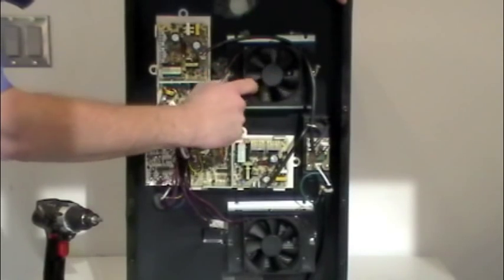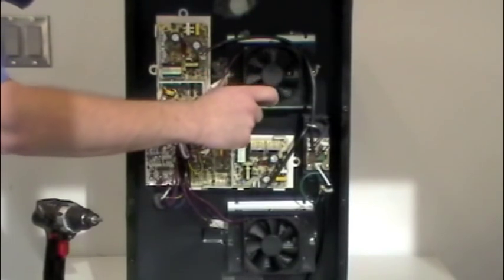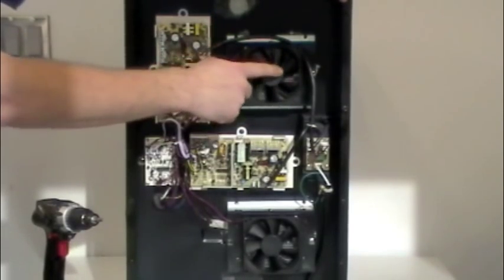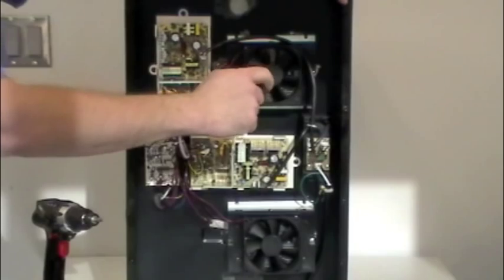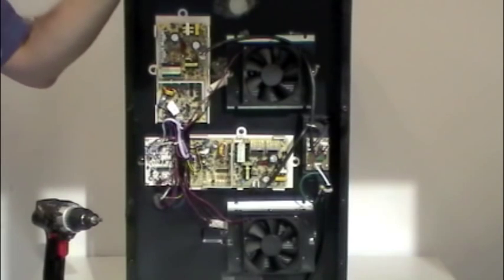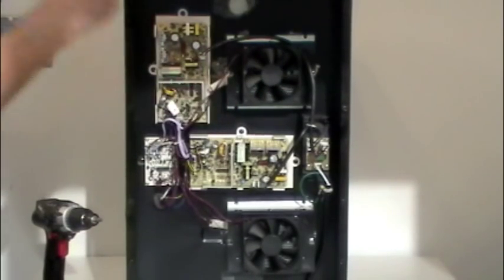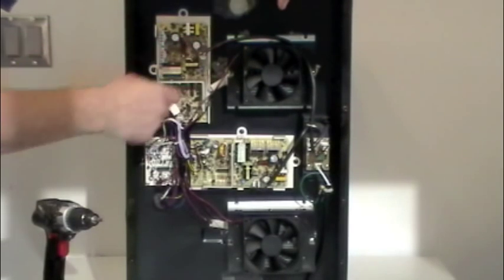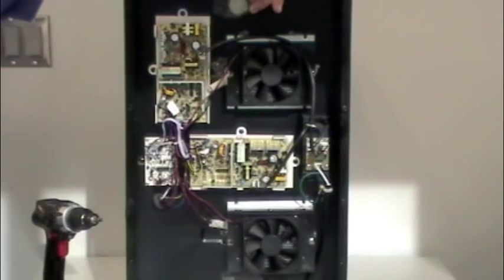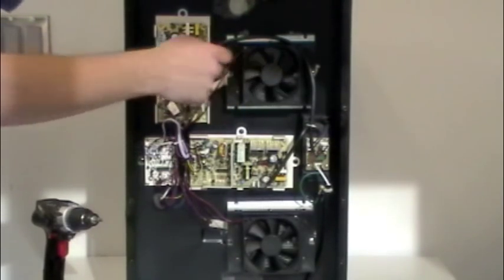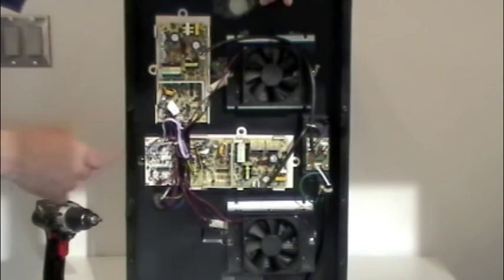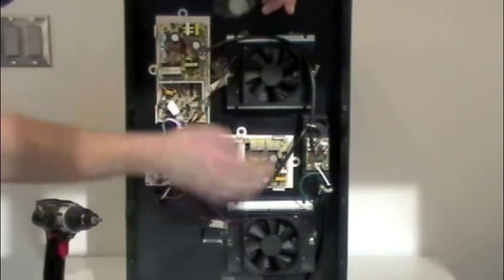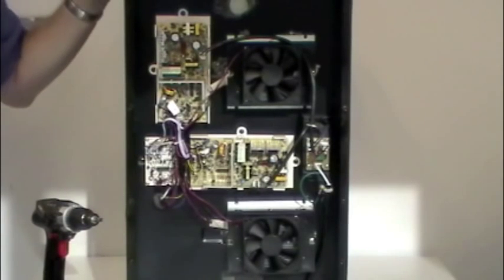By the way, when you spin these fans, they should have a bit of a jerky action. As you can see, it kind of jerks and stops. That's normal. If you spin this by hand and you get a grating sound or a growling sound, there's a little cone bearing in the back of this. And what I would do to double check that fan, spin it by hand, listen for the bearing noise. If you hear something in there, what you can do is take this fan off and flip it around. On the back side of this, there's a sticker with a model number. Peel the sticker back, take some silicone lube and give it a quick burst of silicone lube inside this area back in here on the opposite side of this fan. Put the sticker back on and run it. If it gets quiet, we know that's the bearing for sure. If you hear the noise and you hit it with some lubricant and it goes away, then we know the fan's bad for sure. That goes for both of these fans and the two fans inside here.